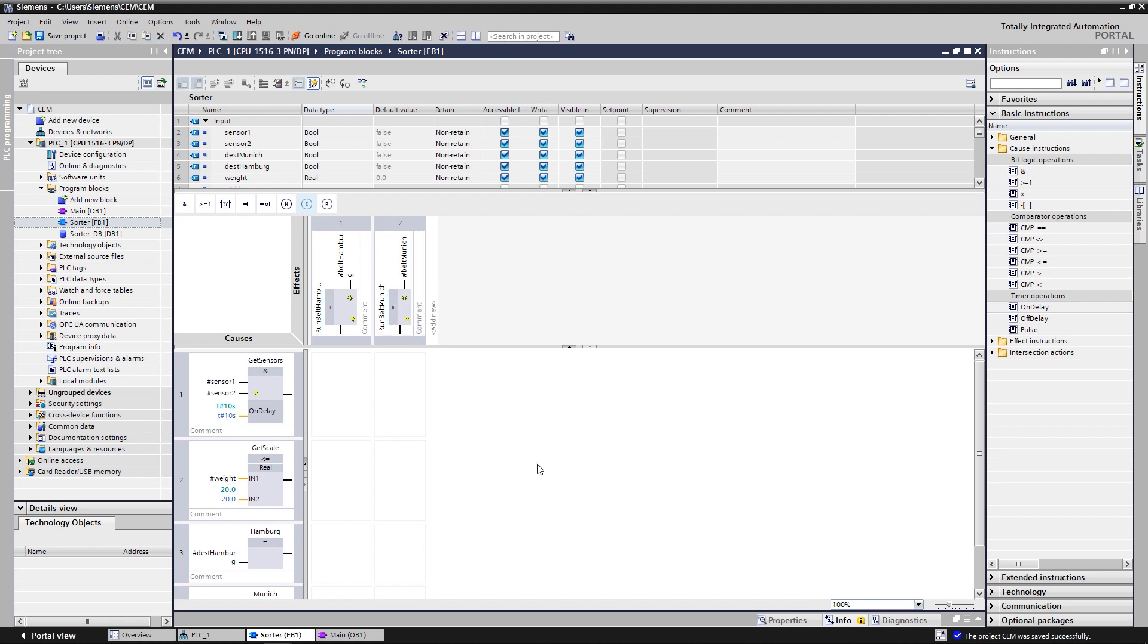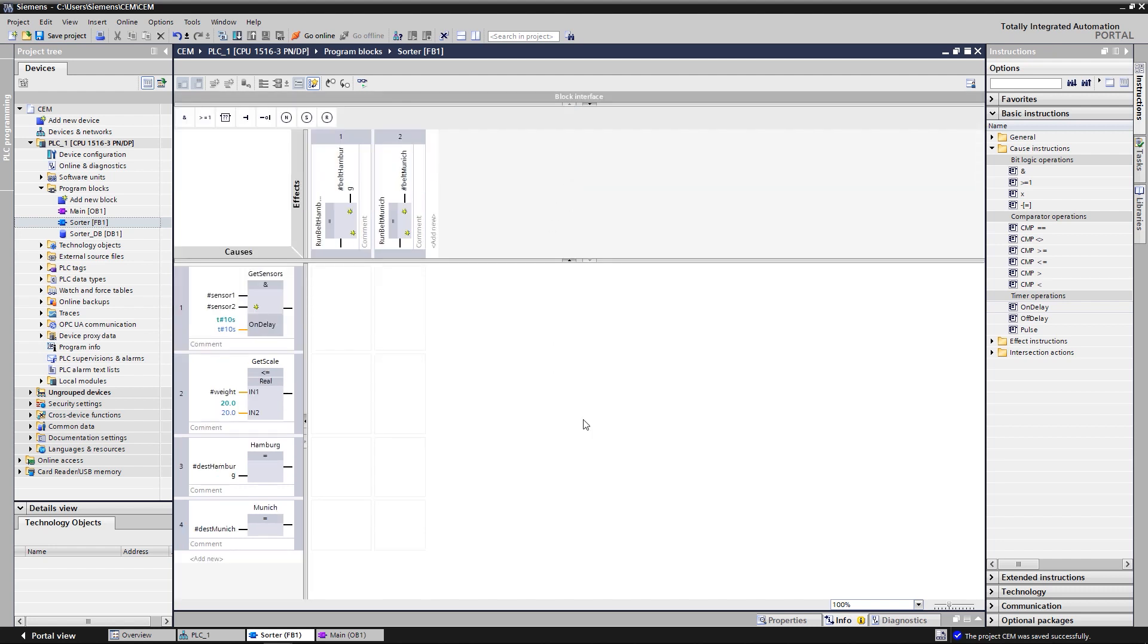Let's now create the intersections. As you remember, the conditions according to the task definition, there are three conditions assigned to each conveyor belt. All three conditions must be fulfilled for the belt to start moving. By default, the intersections of a column are linked by a logical or in CEM. As soon as one of the intersections becomes active, the associated effect is carried out.